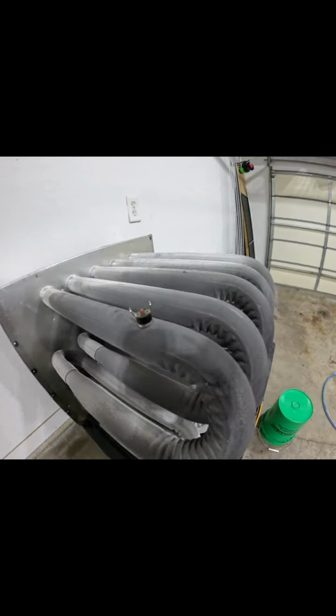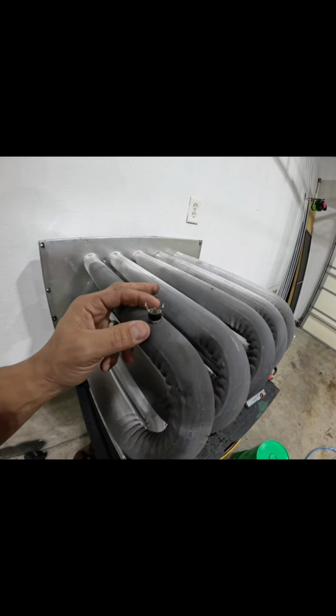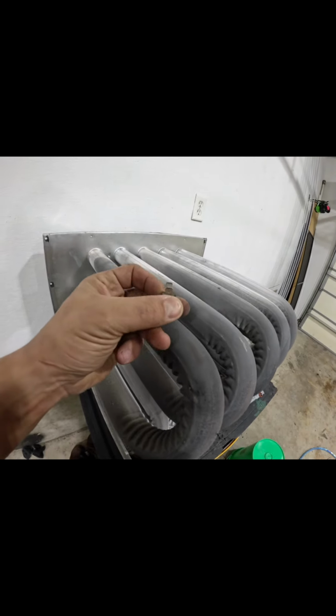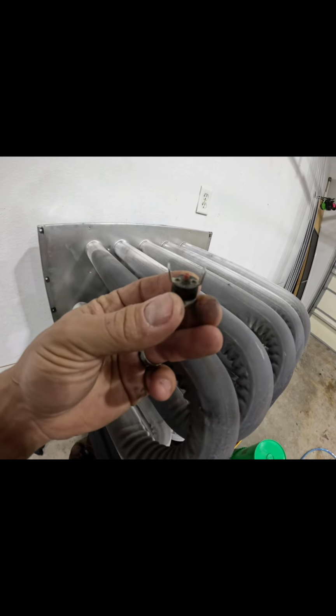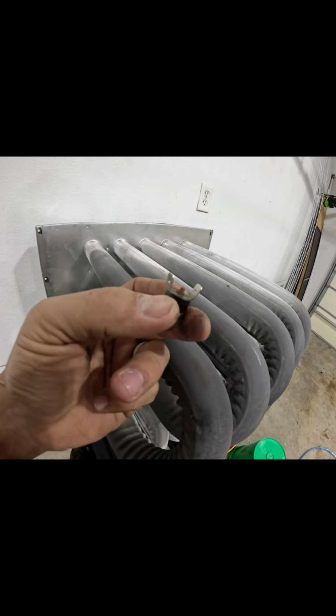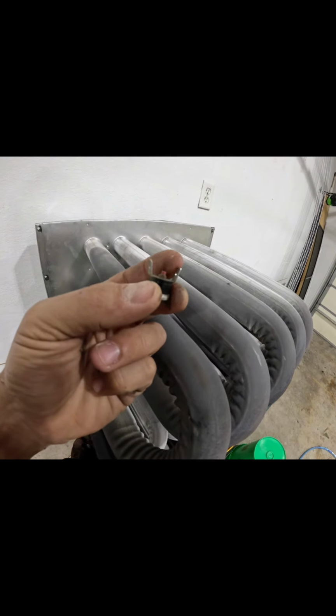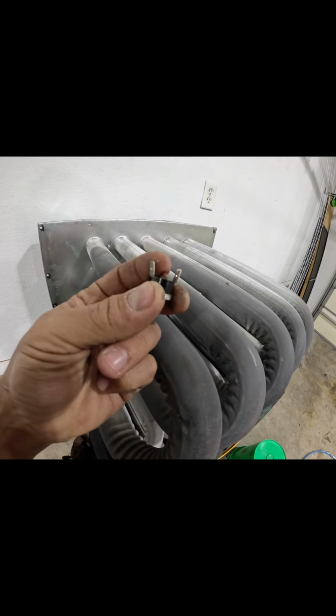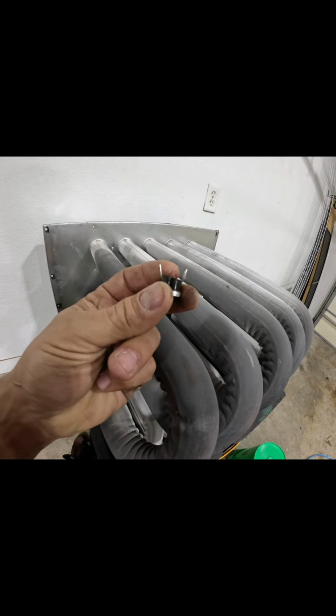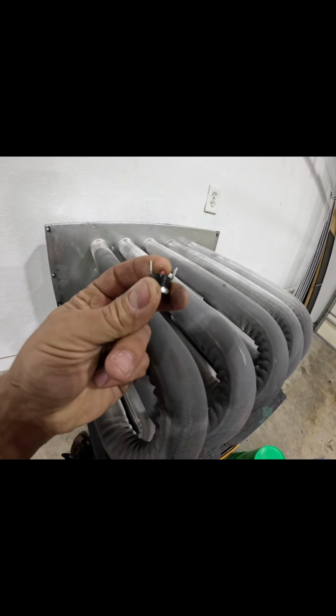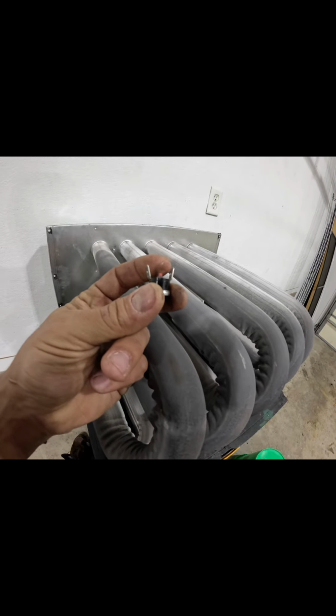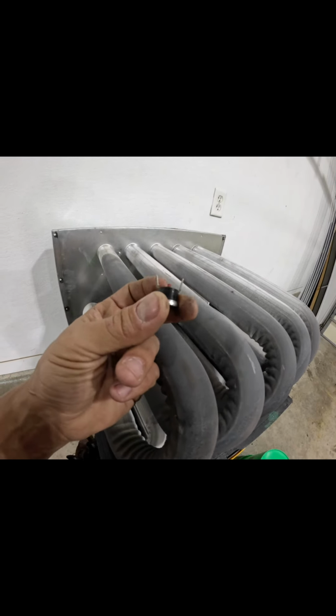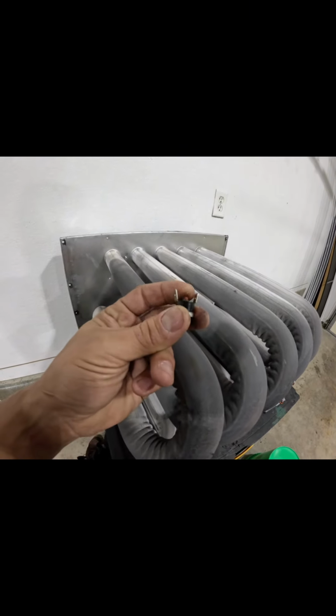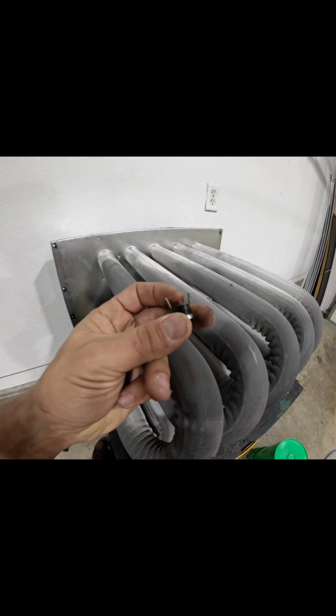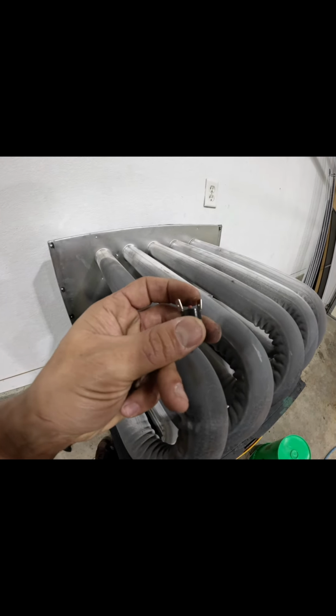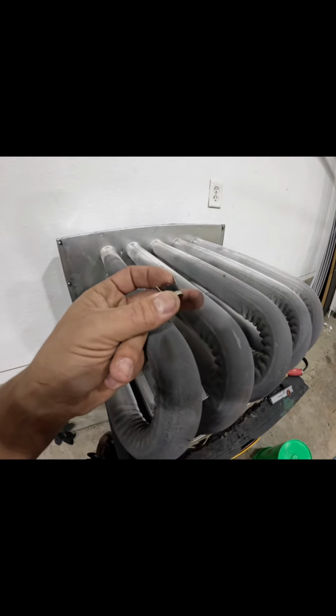Okay, this is what a rollout switch looks like right here. So this is mounted on that burn chamber like we were talking about. It's got the two little wings - power in, power out - and then there's a little button right here. So if this thing pops, you can reset it by pushing the button. It makes a tiny little click, and then you can shut the furnace off, turn it back on, and it will cycle again. This is basically just a fail-safe so that burn chamber doesn't get too hot.